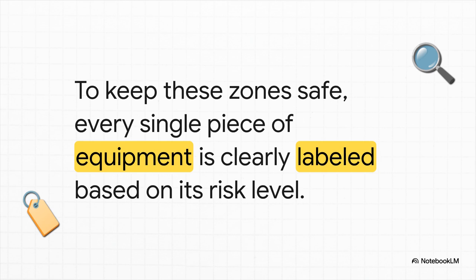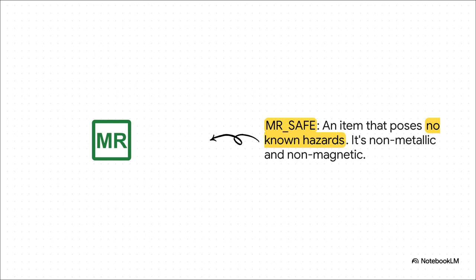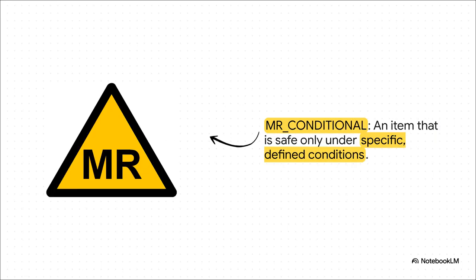There's a really clear, universal labeling system for every single piece of equipment. First up, you've got MR Safe. It's got a green square logo. Super simple. These items are totally non-metallic, non-magnetic, and pose zero risk. Then there's MR Conditional, marked with a yellow triangle. Now this is a big one. These items can be safe, but only if very specific rules are followed. Like, maybe it has to stay a certain distance away from the scanner, or it can only be used with a certain strength of magnet.